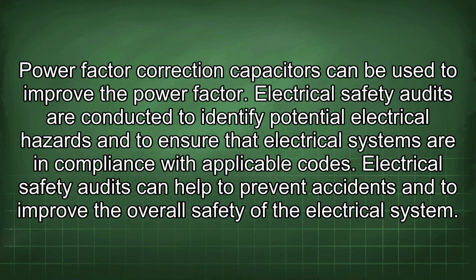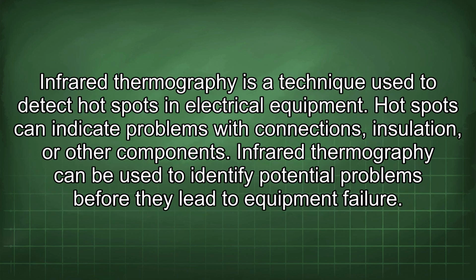Electrical safety audits are conducted to identify potential electrical hazards and to ensure that electrical systems are in compliance with applicable codes. Electrical safety audits can help to prevent accidents and to improve the overall safety of the electrical system. Infrared thermography is a technique used to detect hot spots in electrical equipment. Hot spots can indicate problems with connections, insulation, or other components. Infrared thermography can be used to identify potential problems before they lead to equipment failure.